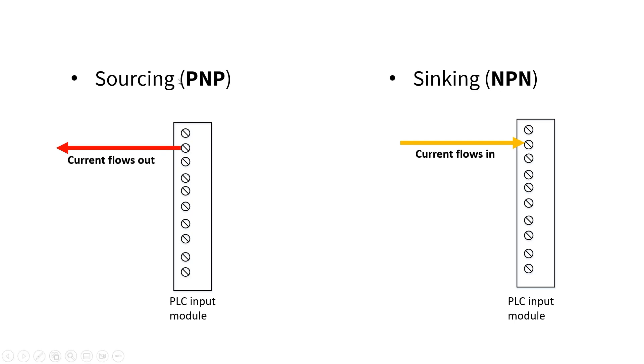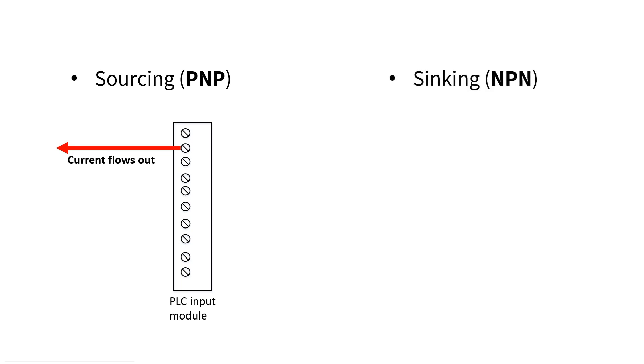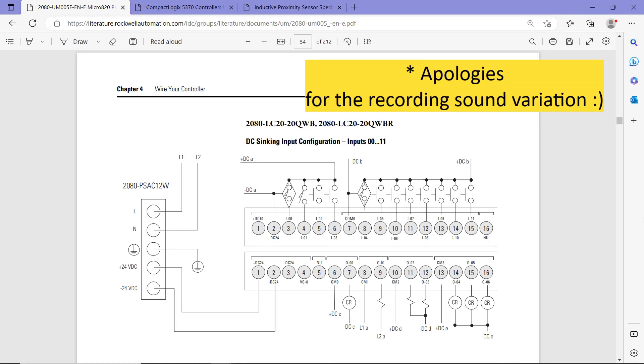For digital sensors, sinking and sourcing — the terms sinking (NPN) and sourcing (PNP) — refer to the direction in which the current flows through the input or output module of a PLC. A sourcing PNP module is when the current flows out of the PLC port, so the port acts as a source. A sinking NPN module is when the current flows into the PLC port — it kind of sinks into the module. This is usually mentioned in the documentation when working with different PLCs.